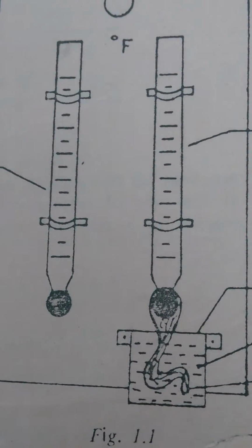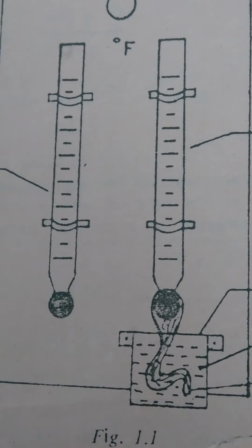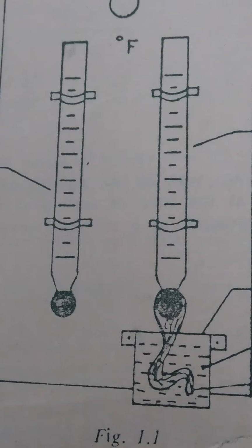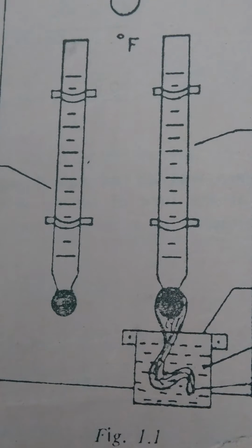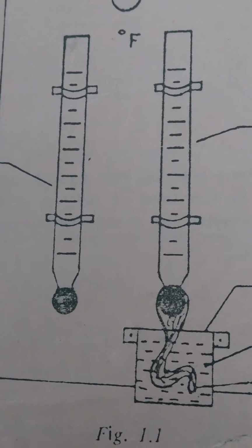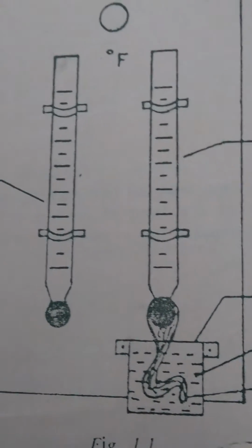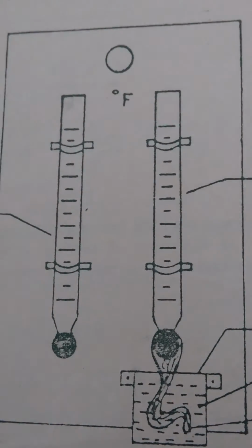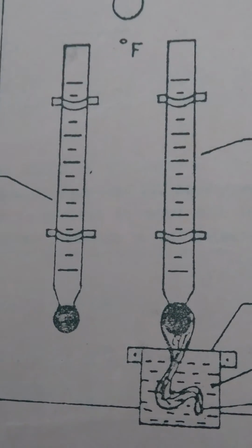The wet bulb thermometer shows a temperature less than the dry bulb temperature and is known as the wet bulb temperature. The difference between these two temperatures is noted, and the humidity table is referred to for the dry bulb temperature in one column, and the corresponding difference of the wet bulb indicates the percentage of relative humidity. Now friends, this is all for the working, and for that we have to see the table.